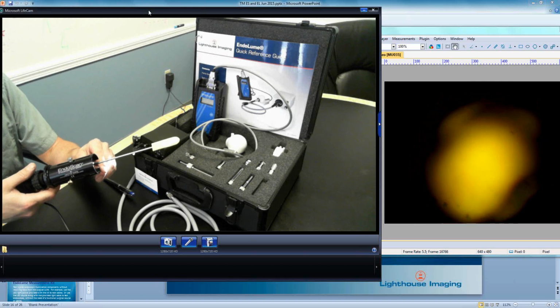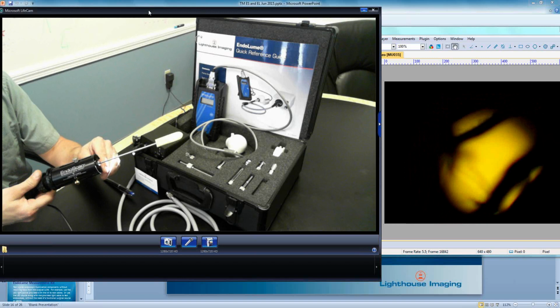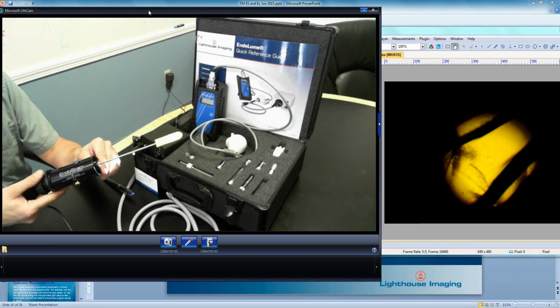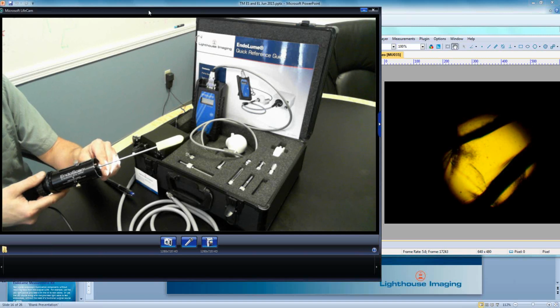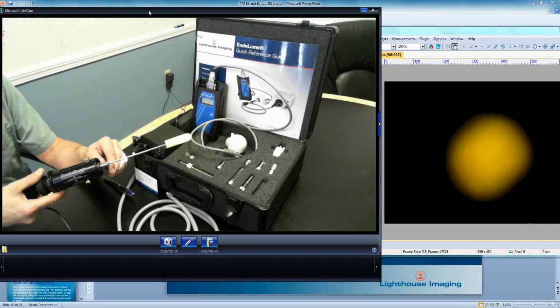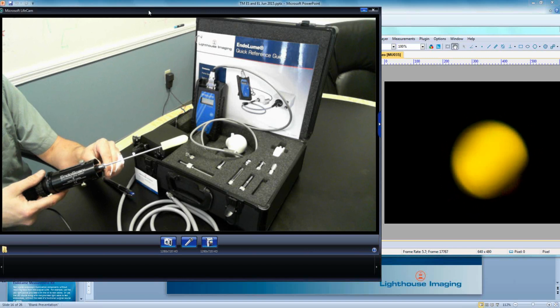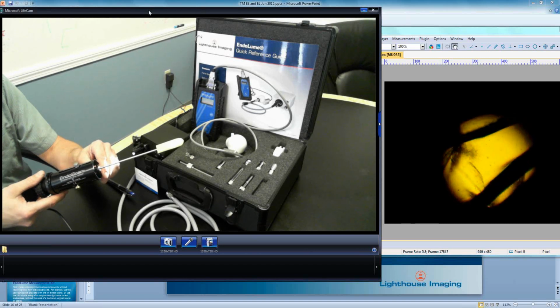However, if we keep looking deeper and deeper into this scope, blow this up a little bit, we're going to see here that this is a cracked rod lens. So we can actually see two black lines in it, they're the actual cracks, and then we can see to the left of the yellow image and a little bit to the lower left of that image some of that kind of fractal fracture pattern occurring. So this scope actually has a broken rod lens inside of it. So by looking inside of it with the EndoScan, we can see that damage. So as you're sliding the scope through the EndoScan, you're seeing it from the close end all the way through the series of rod lenses to the other side.